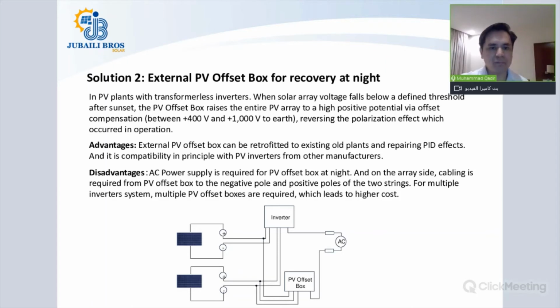When the solar array voltage falls below a certain voltage after the evening, when there is no irradiance available, this PV offset box will sense that and apply positive potential to the negative side of your PV array. This will reverse the polarization effect that happened during the day, and thus it will cure the PID effect. So this happens daily, and it will not affect the operation of your PV plant during the day, and the PID recovery happens at night.